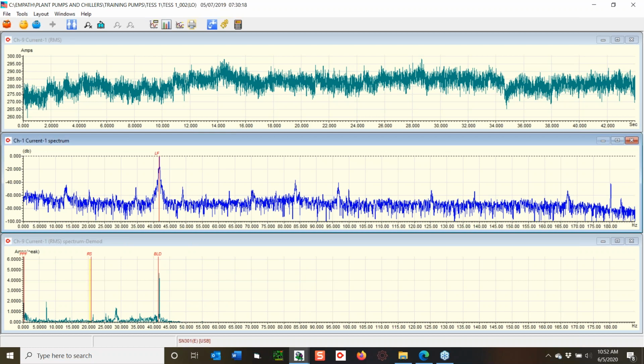And then for VFD, the current is always high. Yes, it is, because this is an RMS meter. And what happens is for this type of data collection, if I used a true RMS data, which would give me an actual value, what ends up happening is it filters out everything. So where I go is I use an RMS type meter, a power analyzer basically.